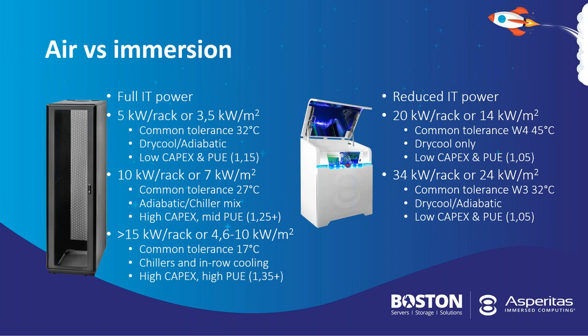If we look at the challenges our market is dealing with today and tomorrow—and this is also what ASHRAE recently published a white paper about—we're going to be more and more challenged on what you can do in a rack. If you're looking at 15 kilowatt or higher racks, there are racks out there, 30, even 40 kilowatts if necessary, but the environment you need to build to sustain that type of density means you're going to be fully dependent on fully chilled water circuits with a maximum tolerance of around 17 degrees Celsius. With very high capex, high PUE, you're going to require in-row cooling strategies, which actually drives down your density per square meter on your white space.